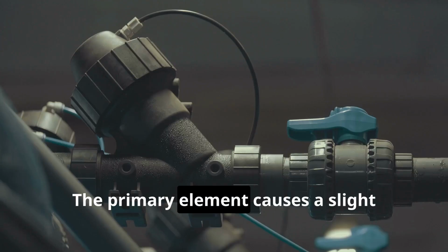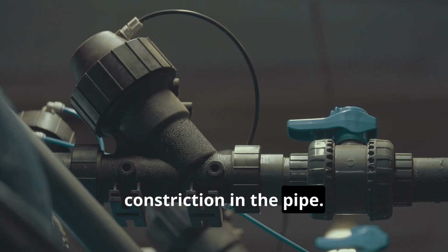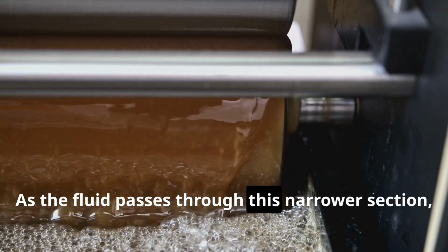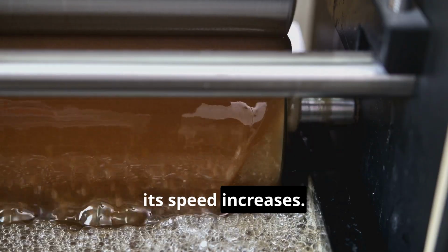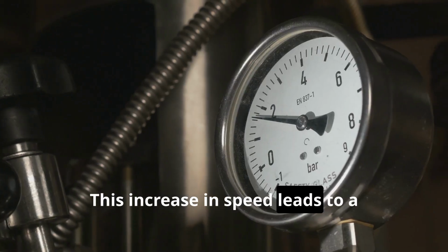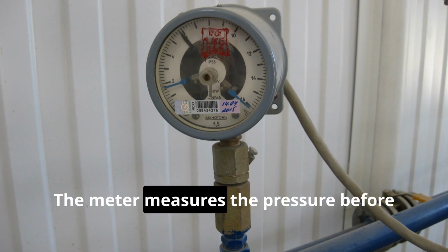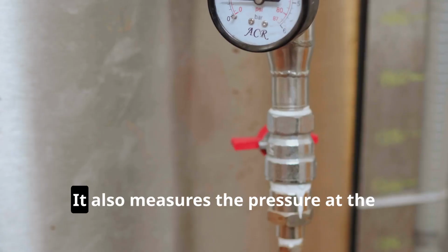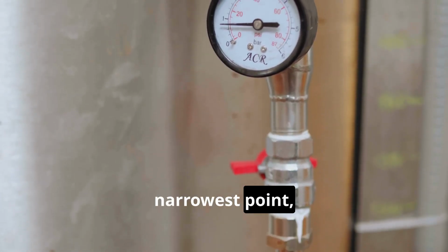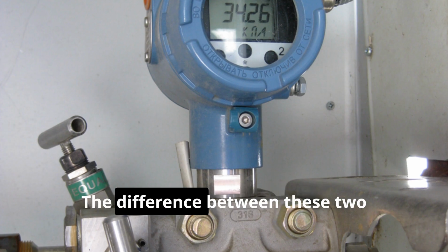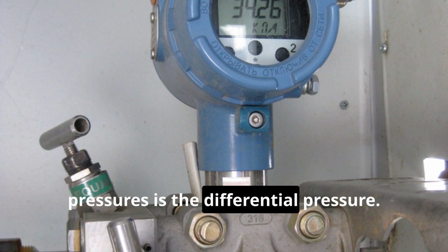The primary element causes a slight constriction in the pipe. As the fluid passes through this narrower section, its speed increases. This increase in speed leads to a decrease in pressure. The meter measures the pressure before the constriction. It also measures the pressure at the narrowest point or slightly downstream. The difference between these two pressures is the differential pressure.